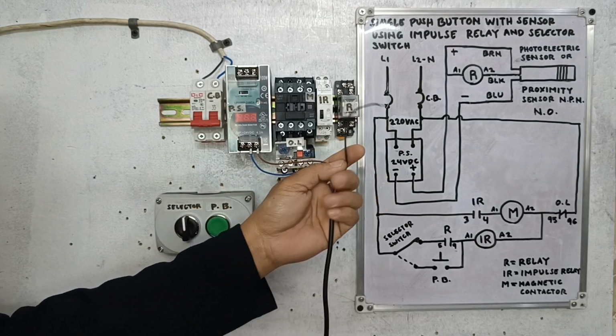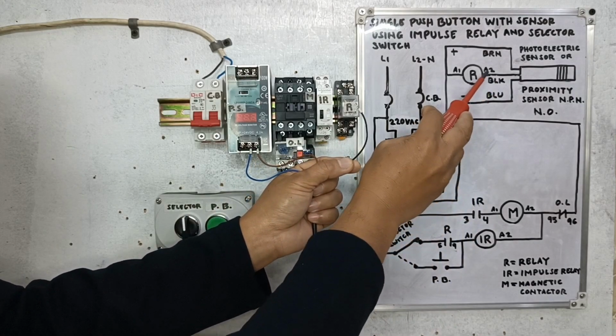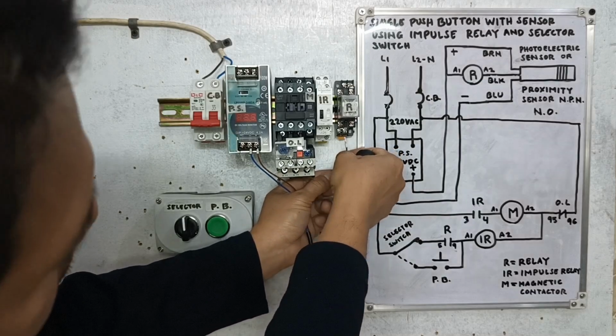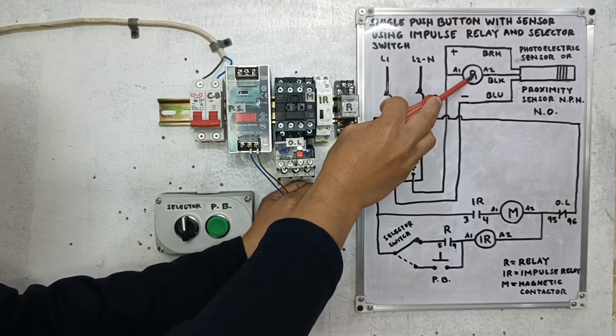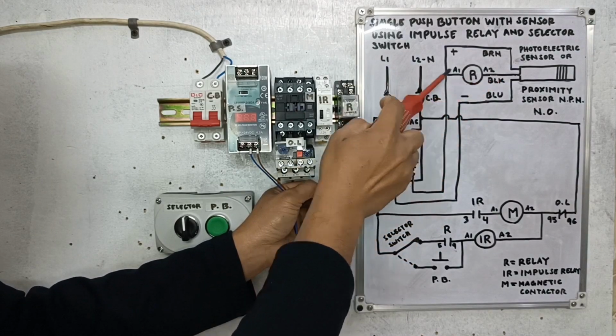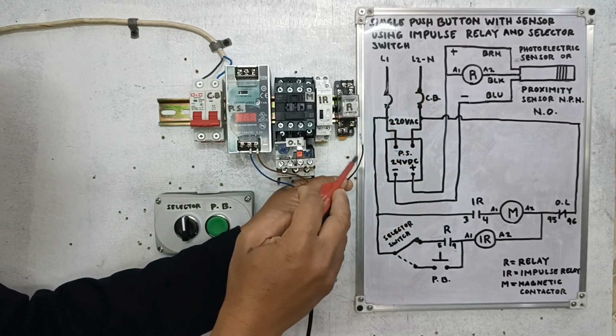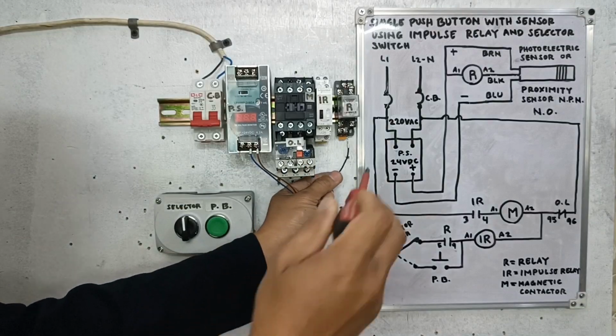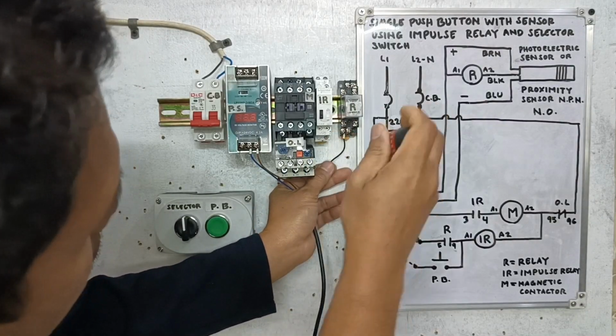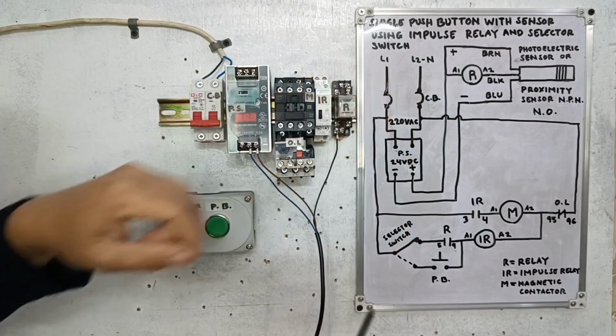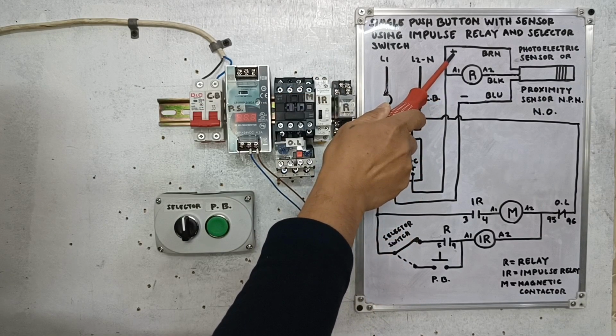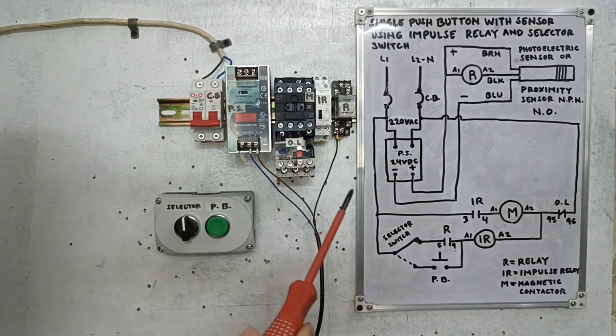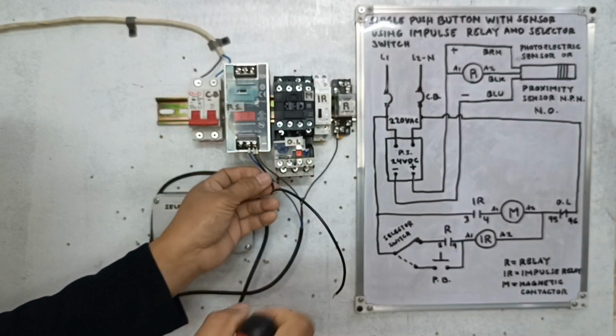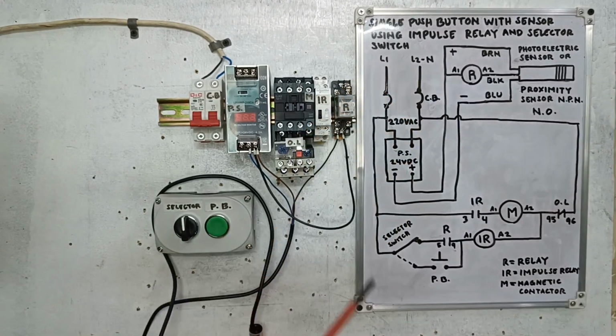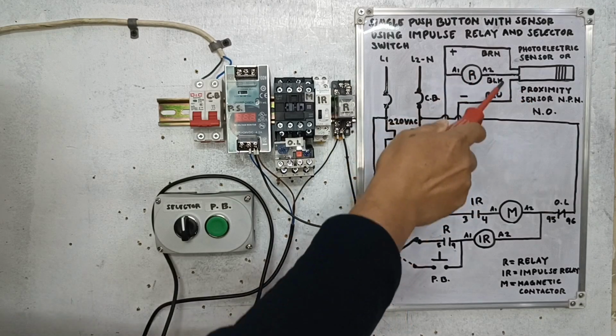And then for the signal, guys, the black wire, we can put to A2 from here, to our relay. This is our relay. Even if the wires are interchanged, it's not a problem. Whether the black wire goes to A2 or A1, no problem, guys. We can connect here to A2 and then we tighten. And then the next, guys, A1 is from the positive. We can connect to the positive from here, from here to here.